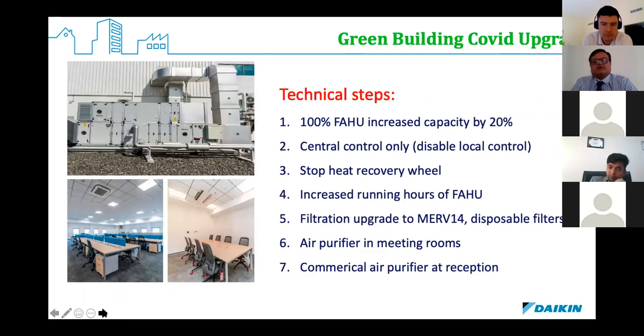On the technical side, our fresh air handling unit uses an EC fan, so we were able to raise the capacity by another 20% and made it run 24 hours. Earlier, for energy savings, we were using it for 12 hours. This gave us better disinfection by adding more outside air, as recommended by ASHRAE. Central control was implemented so that none of the thermostats could be touched by people, or they were fully disabled to stop changing the settings.